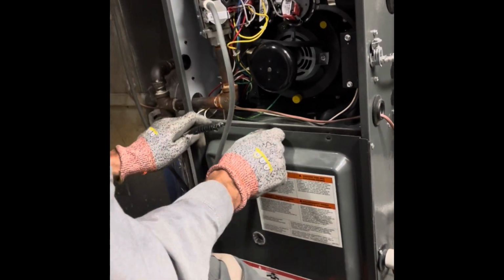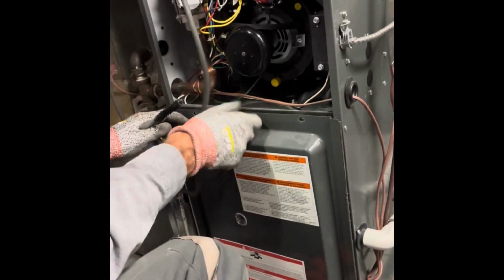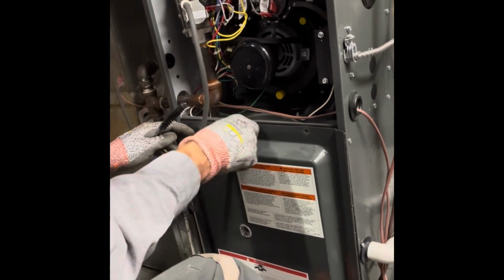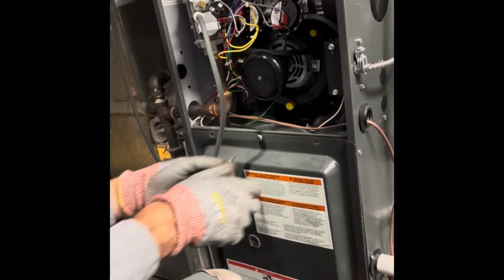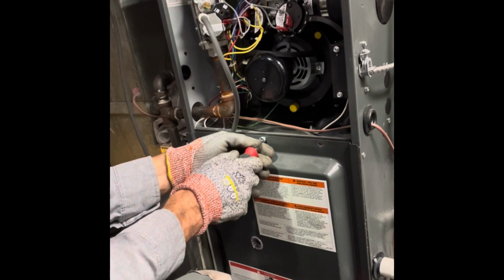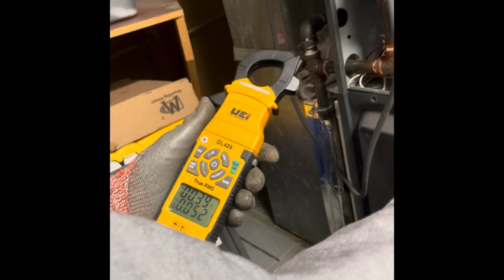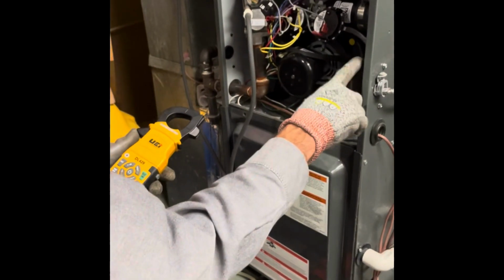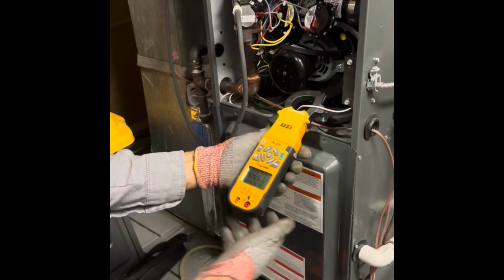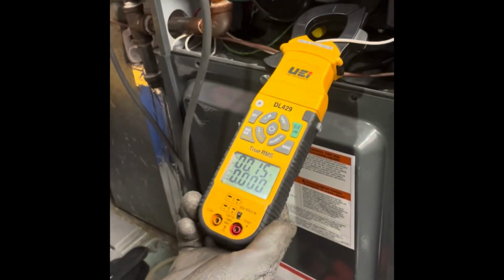So what I'm going to do is put his door back on, and we're going to start getting the maintenance going and get some numbers on his furnace. So we'll close this. The way to check our power consumption is we're going to go to the white wire, which is the neutral on our main power box here. And I'm going to hook my amp meter around there.